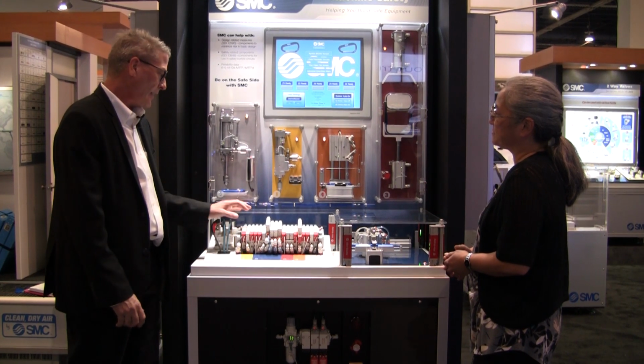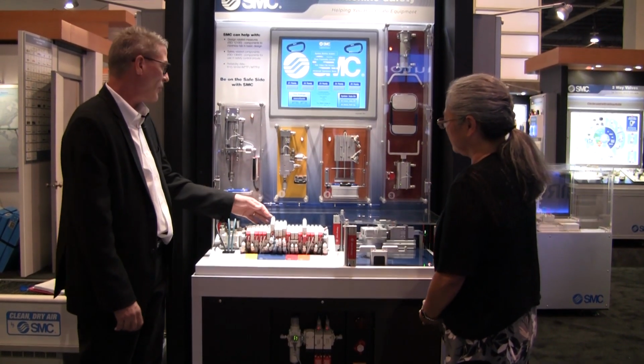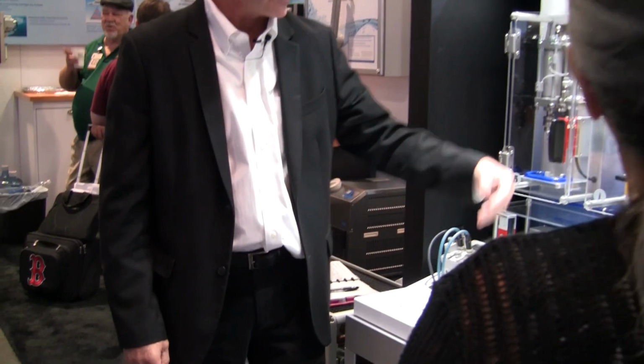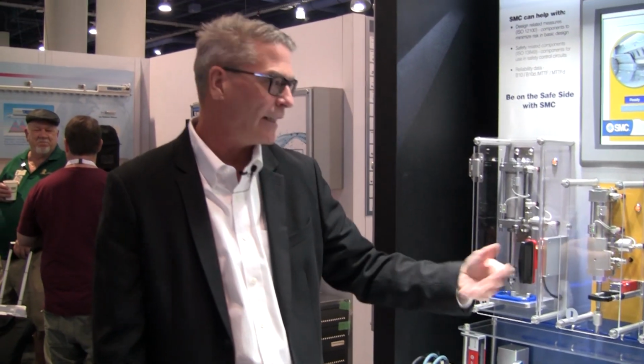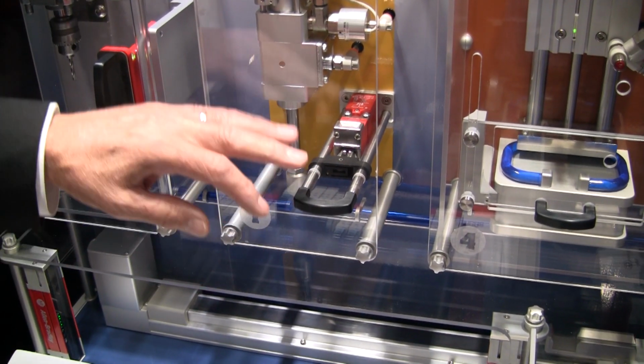What are the trends of today's safety? The newer thinking in safety is to try to localize it to just a particular zone. Rather than venting the entire machine, we may have a localized safety function. For example, if I'm interacting with this cylinder here, I don't necessarily want to pause the entire machine. I want parts to be able to be fed in and out and the rest of the machine to do what it needs to do. So I can come to a safe stop just at one area.